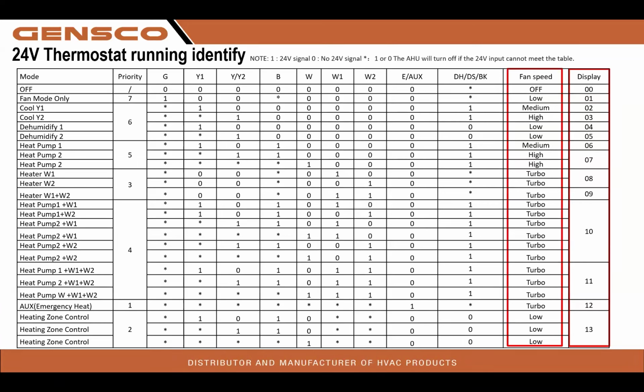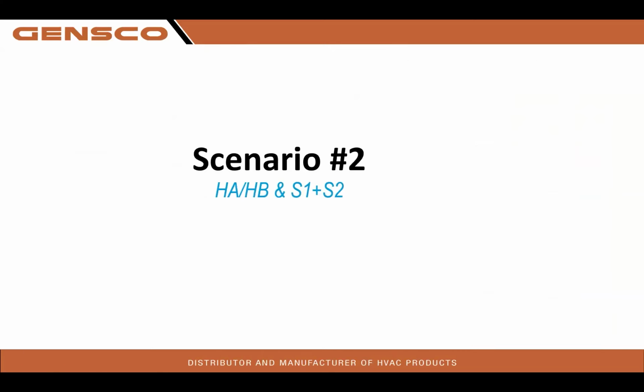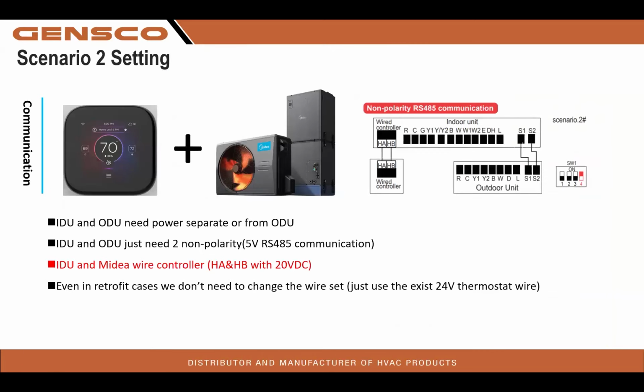"24-volt thermostat running identification." This is all going to display on your indoor 7-segment display. This is the scenario that we prefer you guys using, 2-wire control. HAHB. And by the way, guys, let's stay polarity sensitive. Whatever color we have landed on HA on the indoor unit, let's land on HA on the wired controller. That goes throughout the whole system. Let's stay color sensitive. Let's stay polarity sensitive and not have any mistakes.